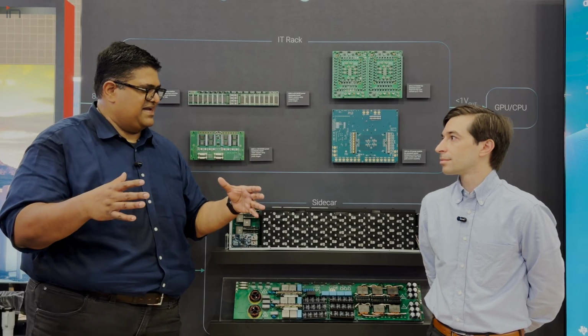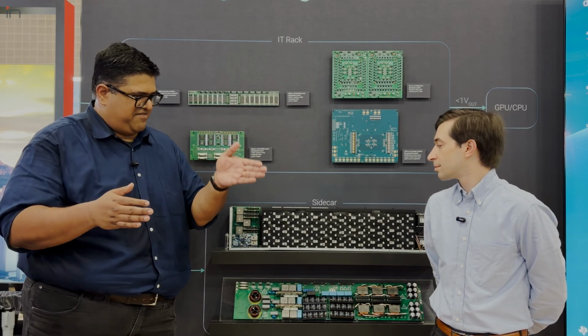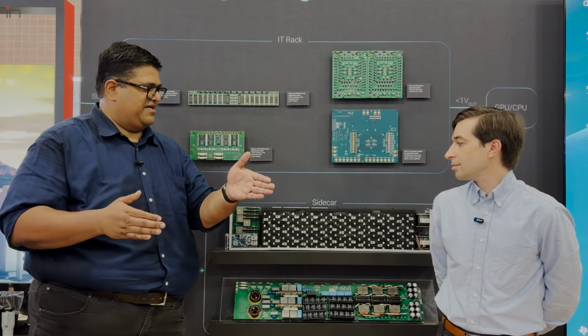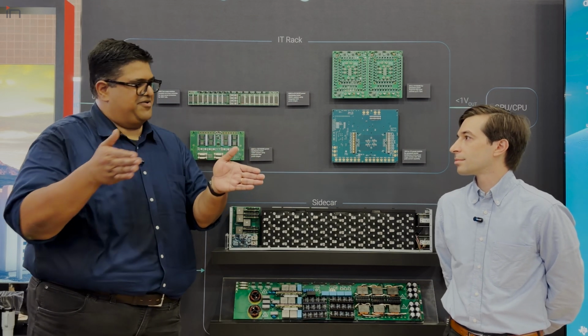If you get 800 volts all the way close to the backplane of a server rack, that's a very different animal from having 12 or 48 volts, which are human safe, versus 800, which needs to be protected in a very different manner. So now everything better be completely uncluttered, completely deterministic, and very clean from the entry point of 800 volts at the backplane all the way down to the processor.